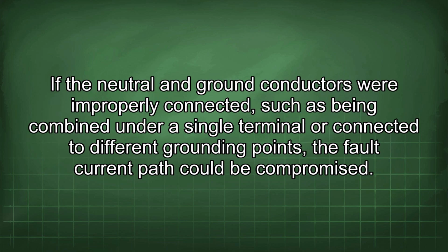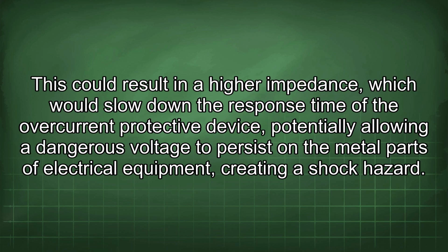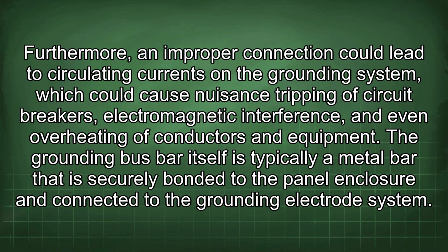If the neutral and ground conductors were improperly connected, such as being combined under a single terminal or connected to different grounding points, the fault current path could be compromised. This could result in a higher impedance, which would slow down the response time of the overcurrent protective device, potentially allowing a dangerous voltage to persist on the metal parts of electrical equipment, creating a shock hazard. Furthermore, an improper connection could lead to circulating currents in the grounding system, which could cause nuisance tripping of circuit breakers, electromagnetic interference, and even overheating of conductors and equipment.